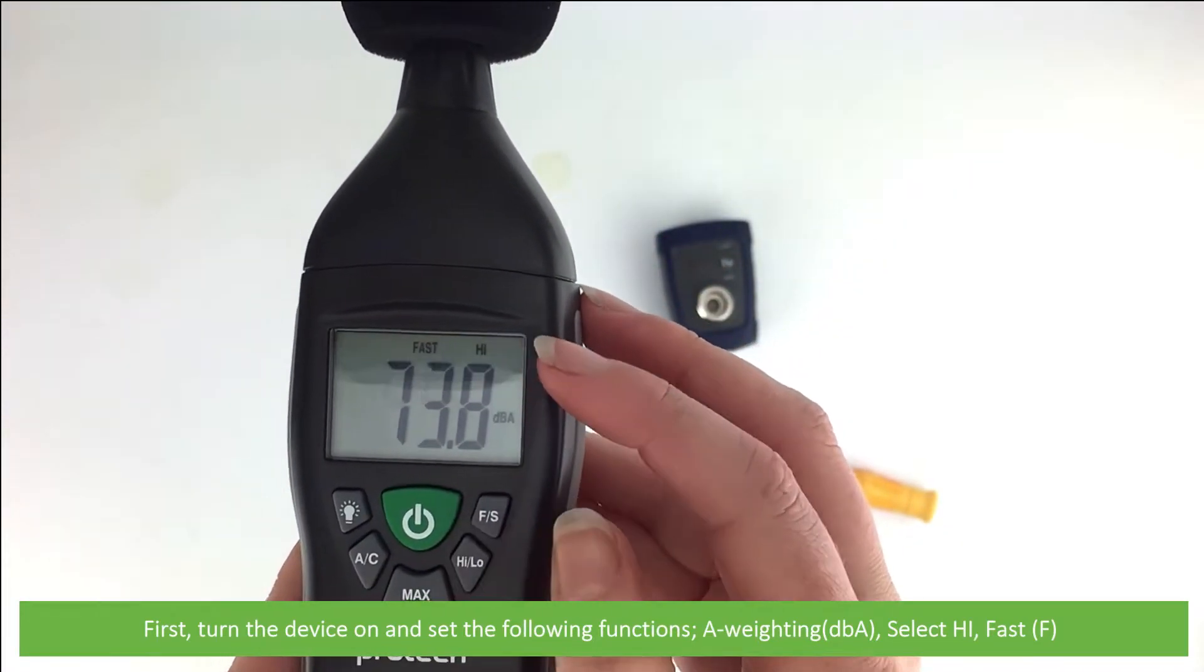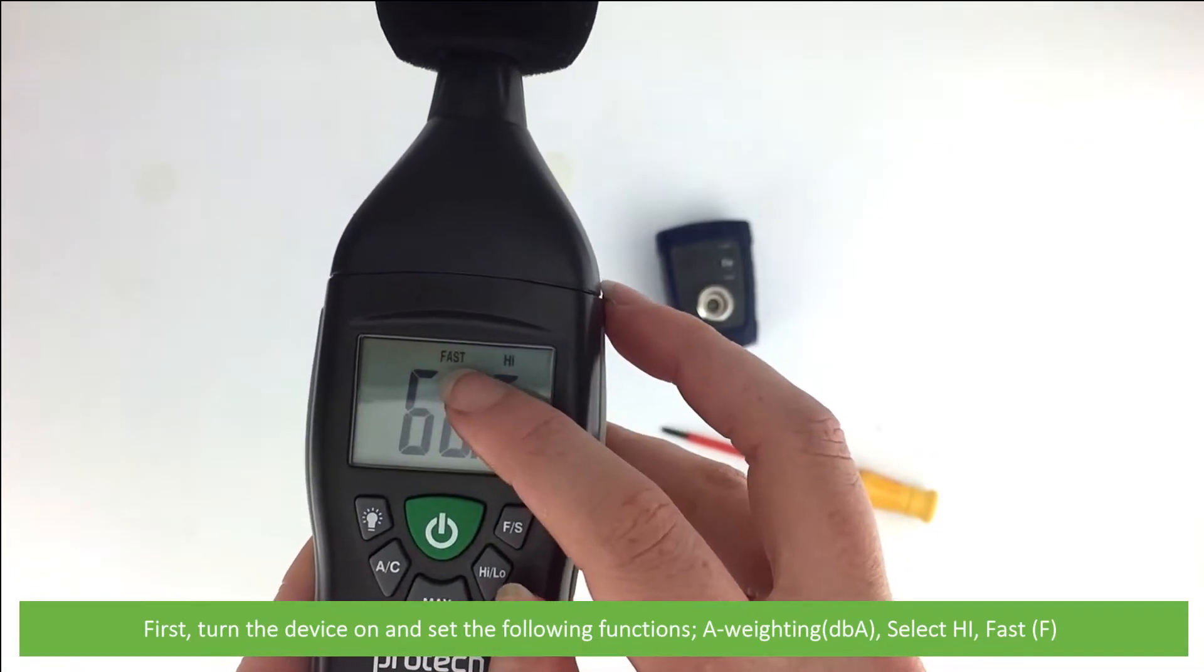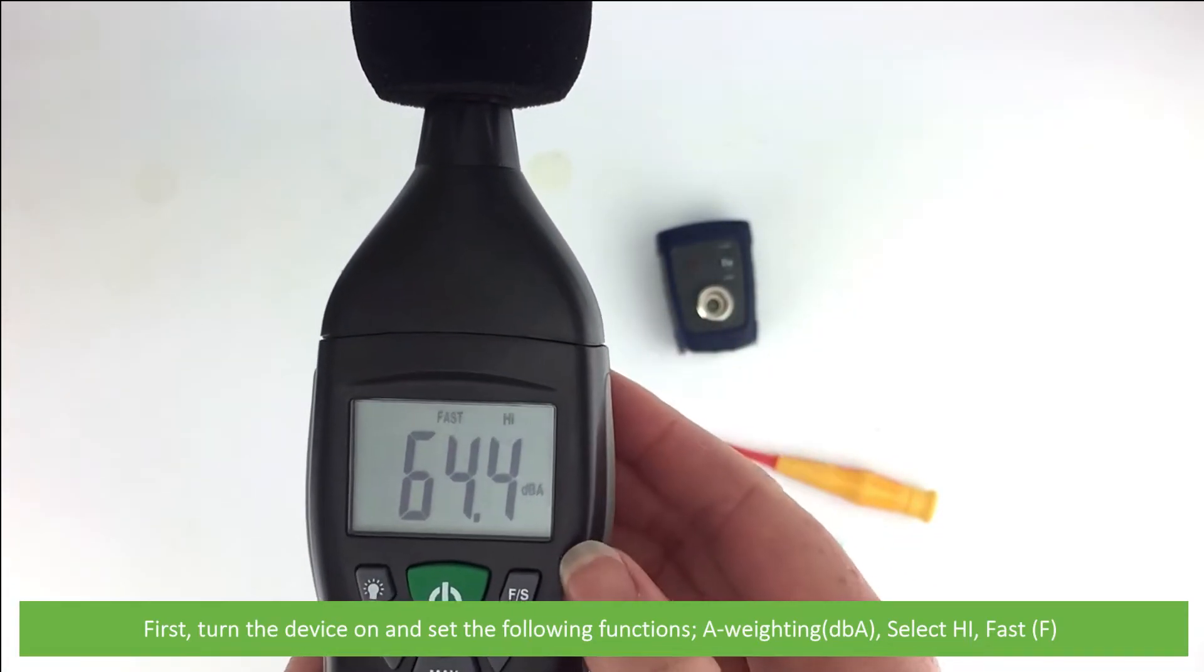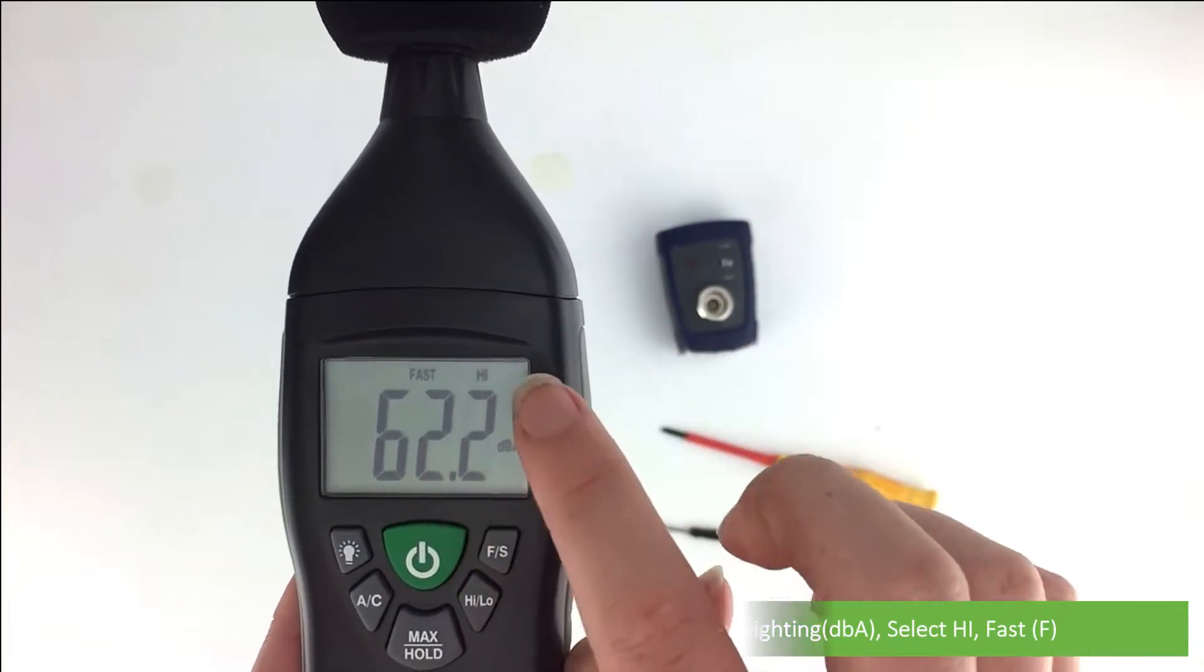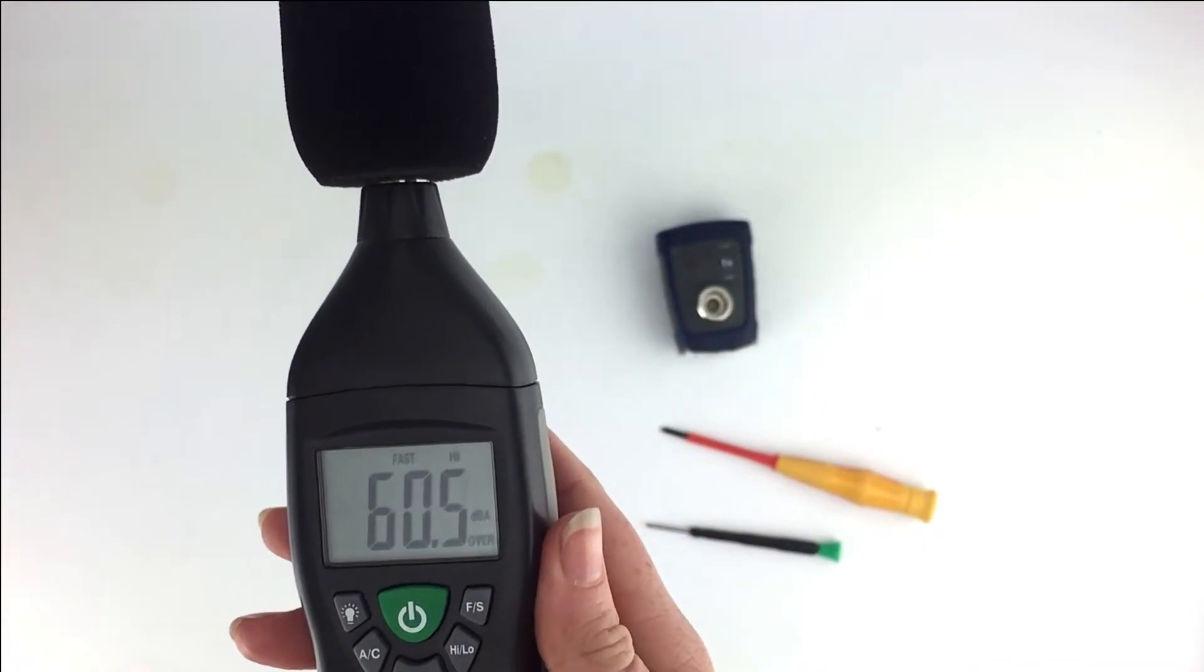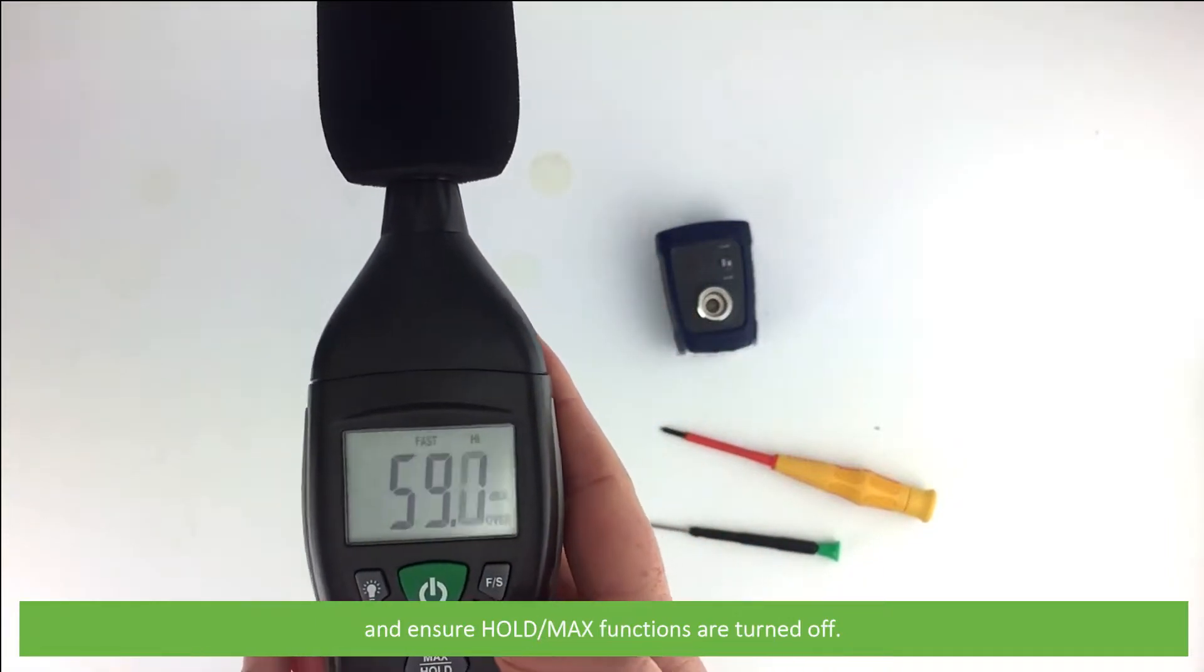Select high for high level measurements, fast this is F, and ensure hold and the maximum functions are turned off.